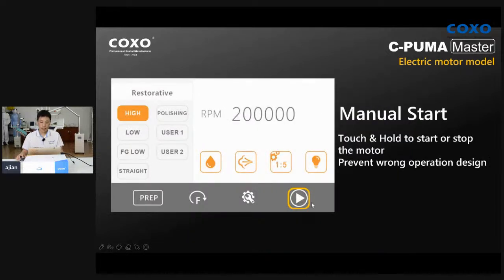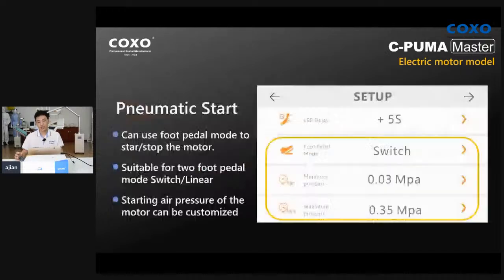This button I mentioned is used for manual start. What does manual start mean? It means the dentist can touch and hold this button for 1 second, then the motor will turn on. Why do you need to hold it for 1 second? Because this is a prevent-wrong-operation design. If it started with just a touch, sometimes it might start when the dentist doesn't want it to. So to start, you must touch and hold for 1 second. We think this is a safe design.